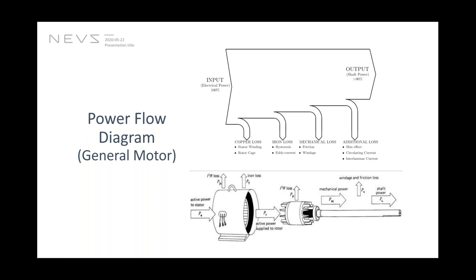So the figure here explains what the losses are. Basically, losses in an electrical machine can be categorized into copper loss, iron loss, and mechanical loss. Copper losses occur when current flows in any of the conductors. Iron losses are due to the hysteresis in the magnetism and circulating currents in the steel lamination, the eddy currents. And mechanical losses, as usual, are the friction in the bearings as well as the windage. Windage means the friction due to the turbulent airflow between the very narrow gap of the stator and rotor.